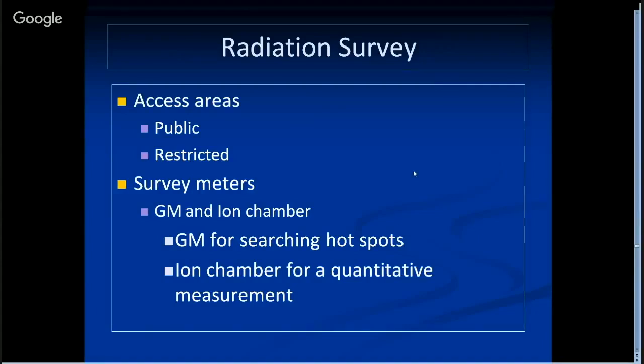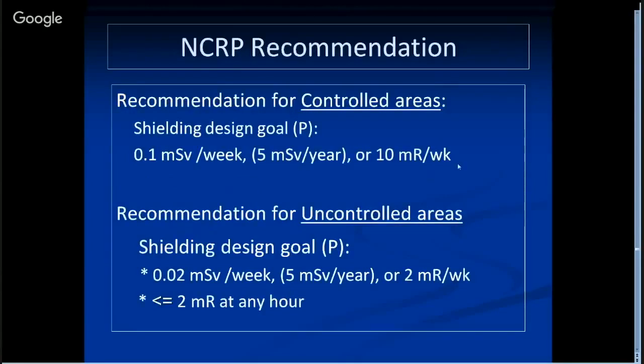The access areas includes public and restricted. NCRP recommends 10 mR per week for the controlled area, and for the uncontrolled area, that's 2 mR per week. Also, you should know that at any hour, the exposure rate shouldn't be greater than 2 mR.